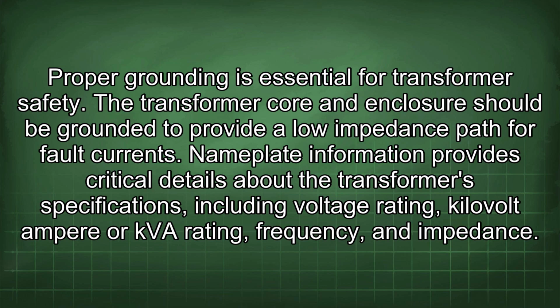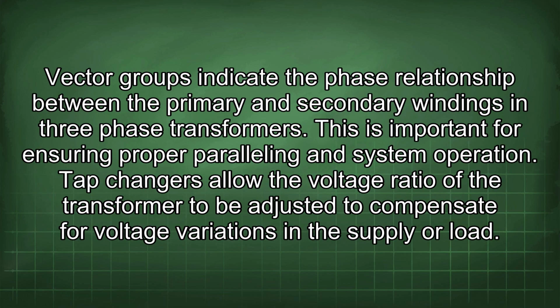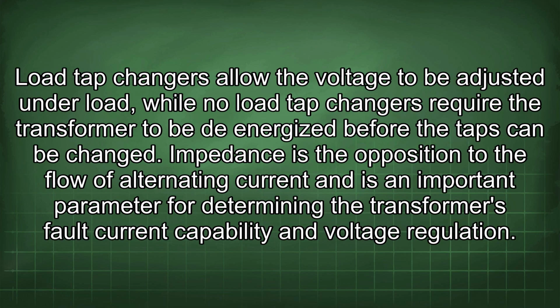Nameplate information provides critical details about the transformer's specifications, including voltage rating, kilovolt ampere or kVA rating, frequency, and impedance. Vector groups indicate the phase relationship between the primary and secondary windings in three-phase transformers. This is important for ensuring proper paralleling and system operation. Tap changers allow the voltage ratio of the transformer to be adjusted to compensate for voltage variations in the supply or load. Load tap changers allow the voltage to be adjusted under load, while no load tap changers require the transformer to be de-energized before the taps can be changed.